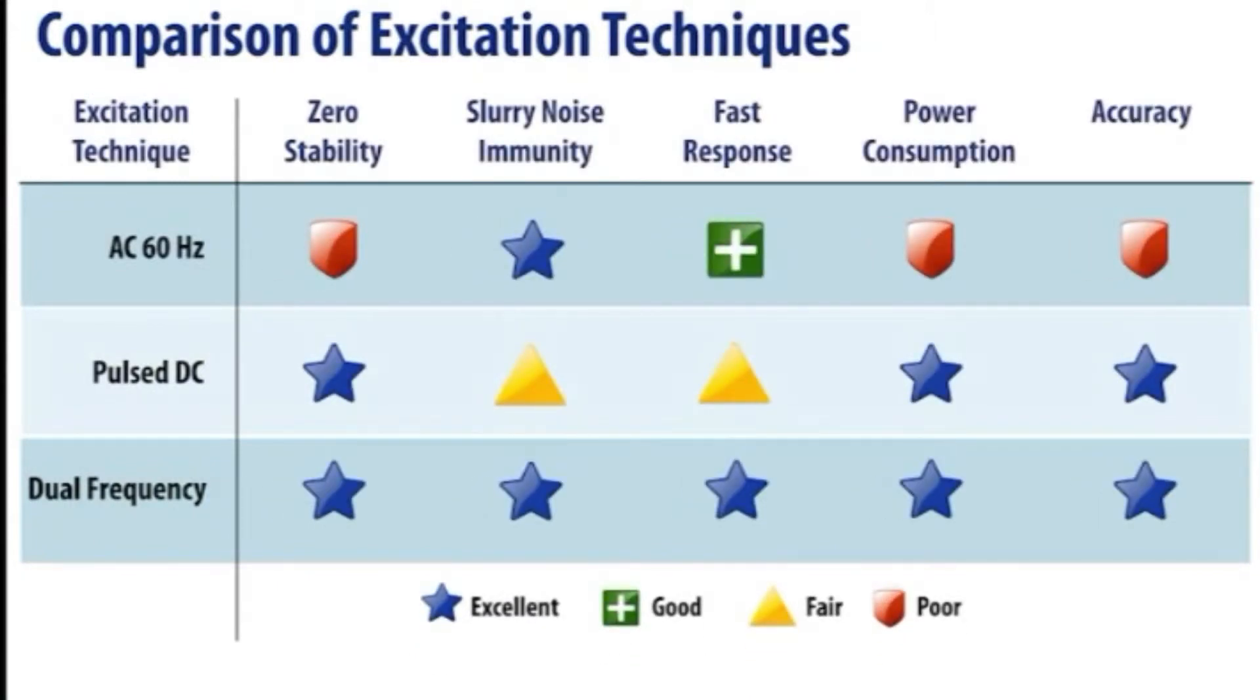The combination of these methods results in the flow noise immunity and fast response of the high frequency excitation method and the high zero stability of the low frequency excitation method simultaneously.